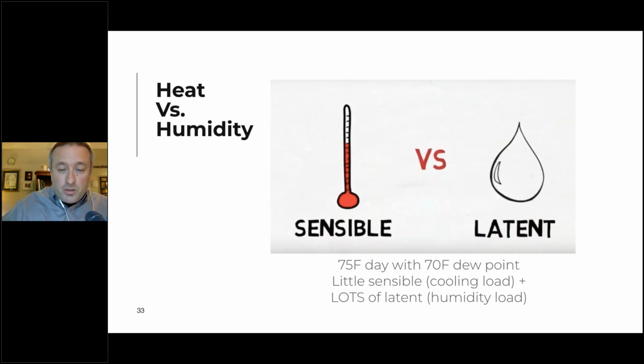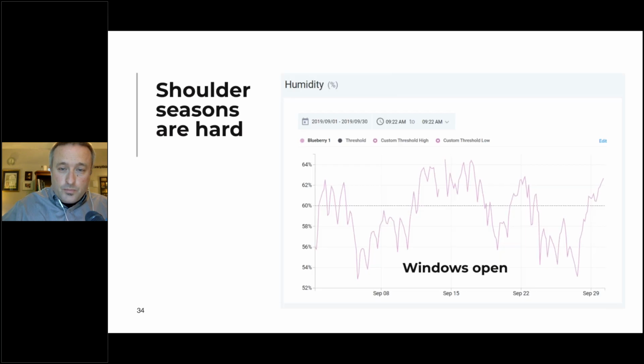So if it's 75 degrees out, but it's very humid, it's a 70-degree dew point, that's extremely difficult because the air conditioner has almost no work to do, but there's a ton of dehumidification that needs to be done. In fact, this weekend, we just had all that happening. It was 72 with a 70-degree dew point most of this weekend, and it just didn't feel good. We've been running windows open, and I was tempted to kick the AC, but I also knew that it wouldn't matter because it can't do that.